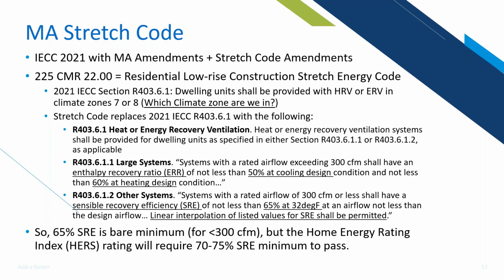Now for 300 CFM or less, you must have a sensible recovery efficiency, SRE, a different metric, of not less than 65% at 32 degrees Fahrenheit, at an airflow not less than the design airflow. And note that our manufacturers can use linear interpolation of the listed values for SRE. So that's the base code. I'm sorry, that's the stretch code requirement.